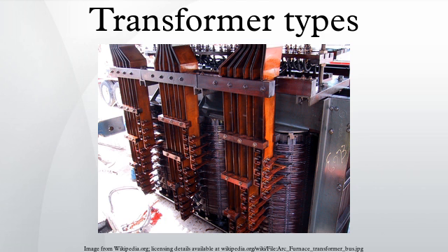Constant voltage transformer. By arranging particular magnetic properties of a transformer core, and installing a ferro-resonant tank circuit, a transformer can be arranged to automatically keep the secondary winding voltage relatively constant for varying primary supply without additional circuitry or manual adjustment. Ferro-resonant transformers run hotter than standard power transformers, because regulating action depends on core saturation, which reduces efficiency. The output waveform is heavily distorted unless careful measures are taken to prevent this. Saturating transformers provide a simple rugged method to stabilize an AC power supply.